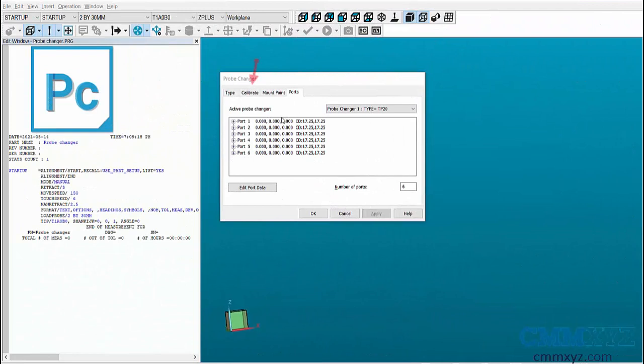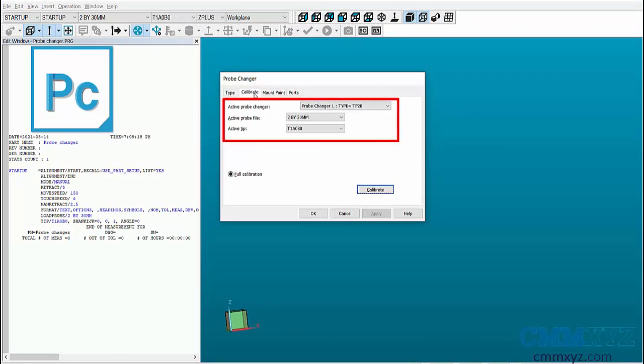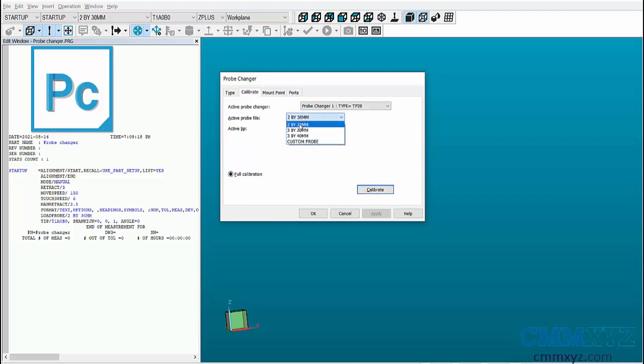Go to the Calibration tab and select the active probe changer and the active probe file, that is 2 by 30 millimeters, and the orientation of the probe used for calibration, that is A0 B0. Then click on Calibrate to calibrate the probe changer.